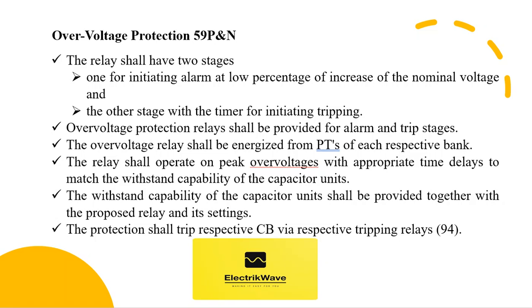The over voltage protection is to be provided in the scheme of protection with the fundamental voltage sensor with a timer with adjustable time settings. The relay shall have two stages: one for initiating alarm at a low percentage of increase of the nominal voltage, and the other stage with the timer for initiating tripping. Over voltage protection relays shall be provided for alarm and trip stages. The over voltage relay shall be energized from the potential transformer of each respective bank. The relay shall operate on peak over voltages with appropriate time delays to match the withstand capability of the capacitor units. The withstand capability of the capacitor units shall be provided together with the proposed relay and its settings. The protection shall trip the respective circuit breaker via respective tripping relays.